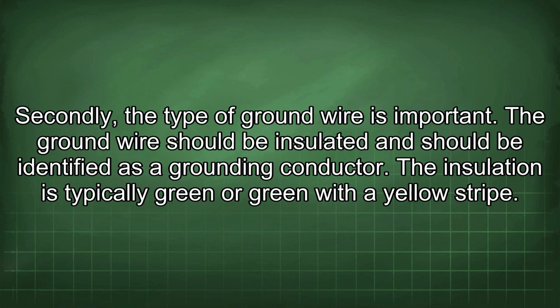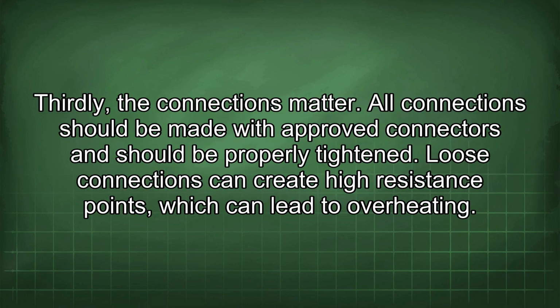Secondly, the type of ground wire is important. The ground wire should be insulated and should be identified as a grounding conductor. The insulation is typically green or green with a yellow stripe. Thirdly, the connections matter. All connections should be made with approved connectors and should be properly tightened. Loose connections can create high resistance points, which can lead to overheating.